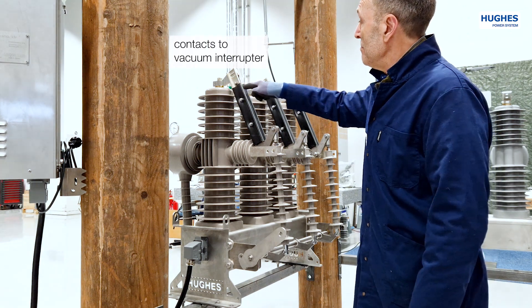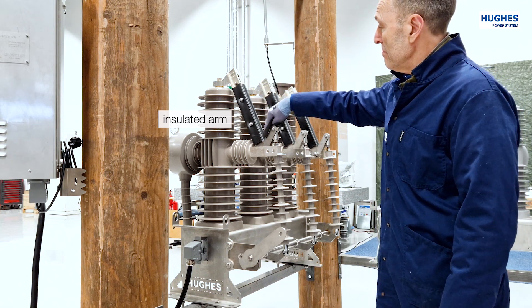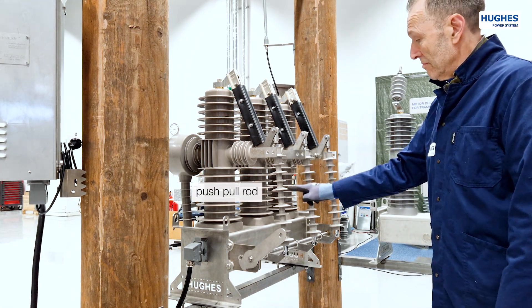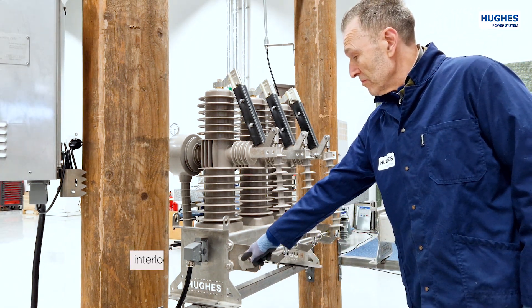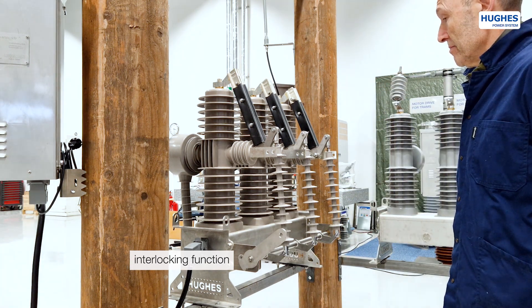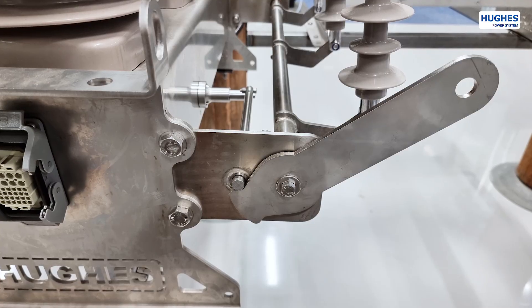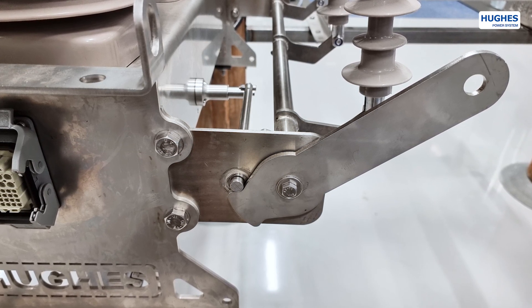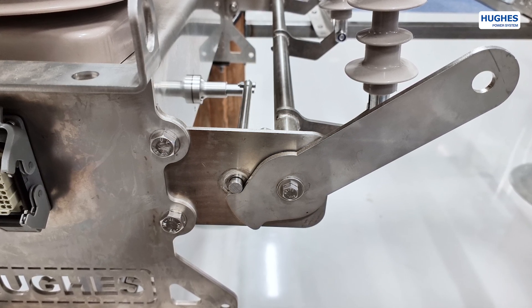At the top of the disconnector switch there are contacts to the vacuum interrupter. The arm of the disconnector is insulated to protect from wild animals and birds. The lower part consists of a disconnector push-pull operation rod and a line connector lug. Here is a demonstration of the interlocking function between the vacuum interrupter circuit breaker and the disconnector, performed via the locking pin. When the circuit breaker is on, the pin goes out and locks the disconnector operation arm. This interlocking function is very important for safety because it ensures that the disconnector can never be opened when there is current in the line.